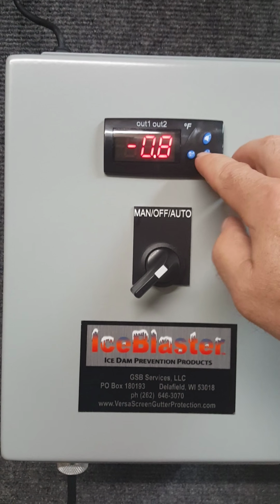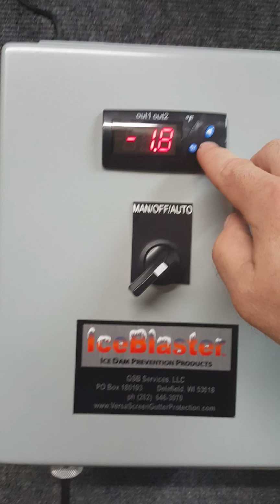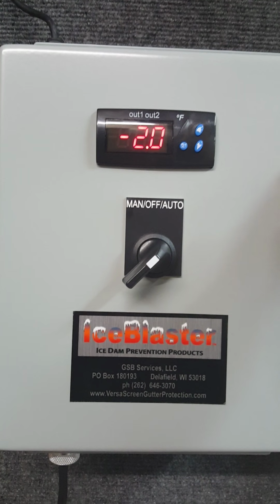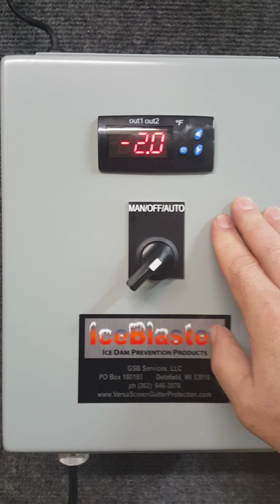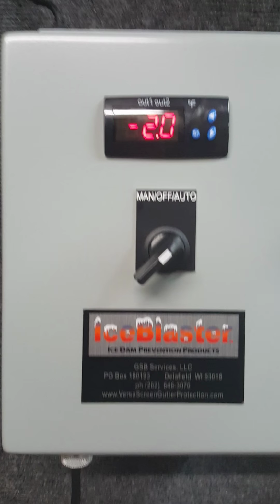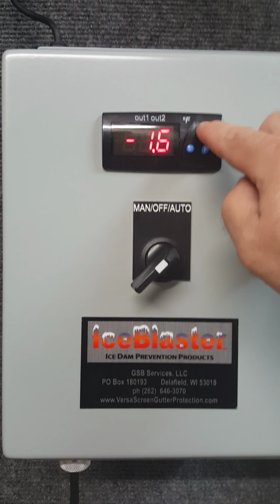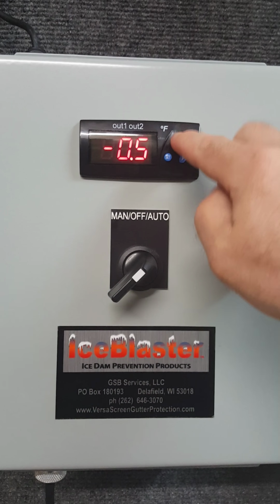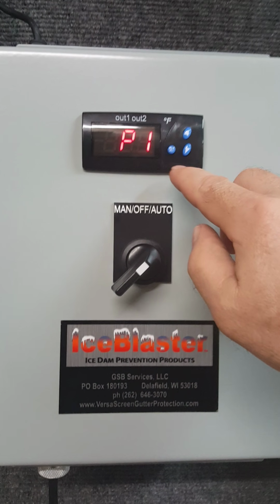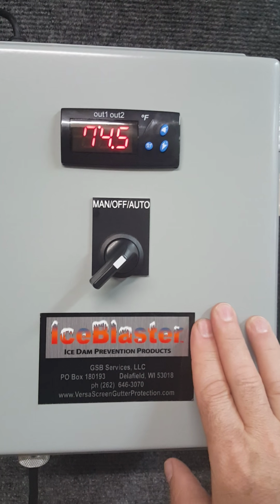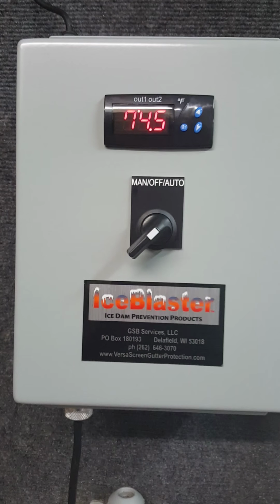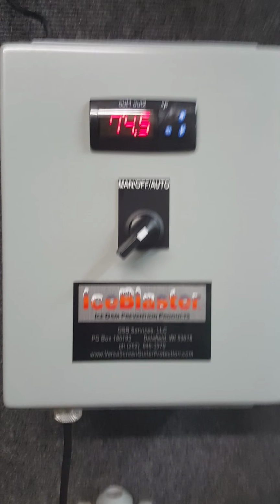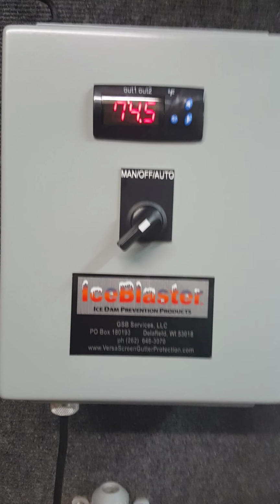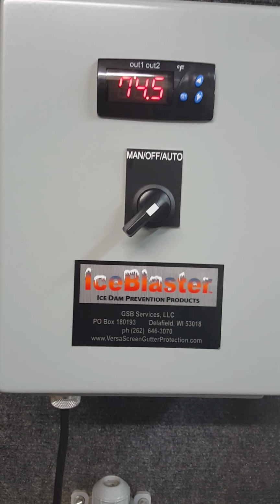If it's reading high, we would dial down. If it's reading high 2 degrees, we'd calibrate it and go to that point. And then that would readjust the reading that it's taking. So we're going to just leave it at 0 for the time being. And then to get it back to that, you hit the set and the arrow key. So it can calibrate, which is a really nice feature, because sometimes when you put these probes, it's not reading what actual ambient temperature is.